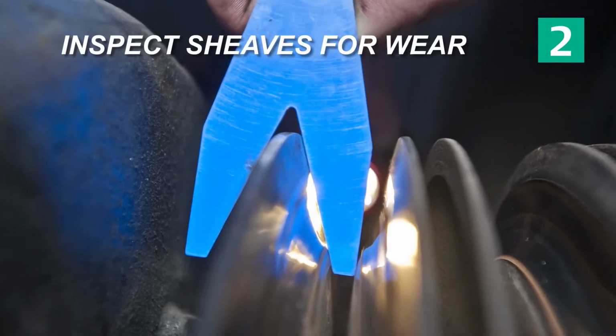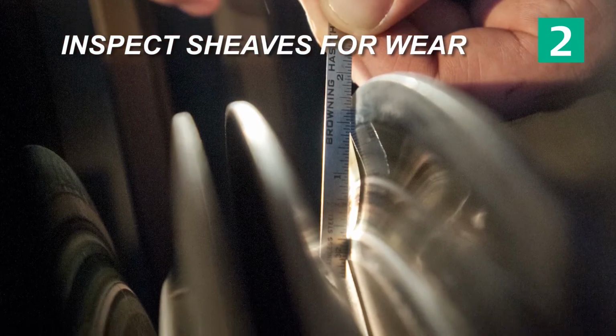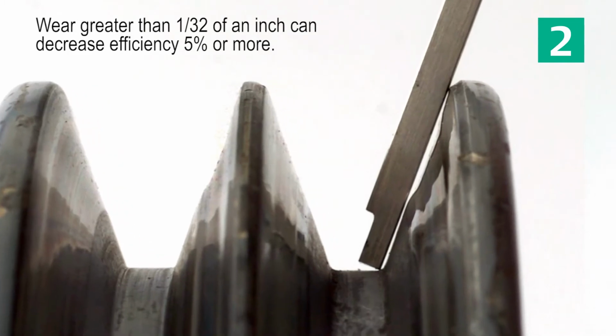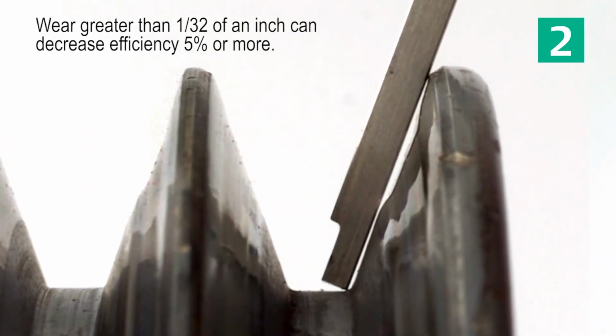The second step is to inspect sheaves for wear. Worn sheaves allow belt slip. Wear greater than 1/32 of an inch can decrease efficiency 5% or more.